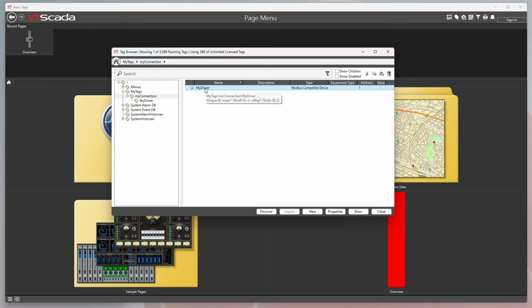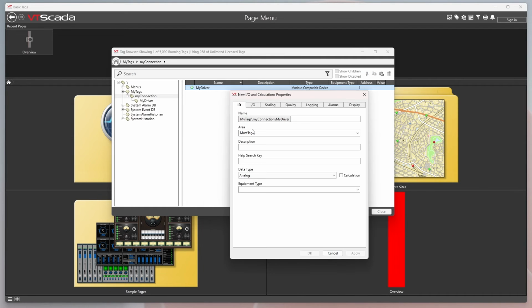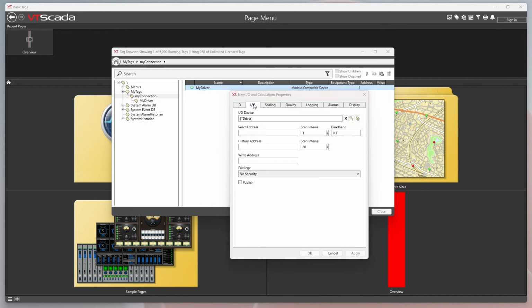As we're adding, next up, a really common thing is to put all of the IO tags for that driver as children of the driver so that you don't have to connect each one individually. So in this case, we'll say new child, and we're going to click IO and calculations, and we will select an analog here, and we're going to call this my values.